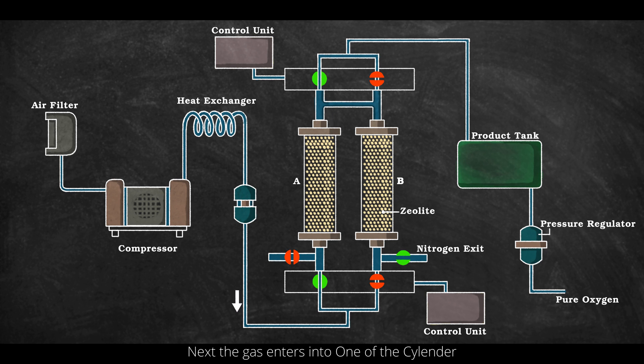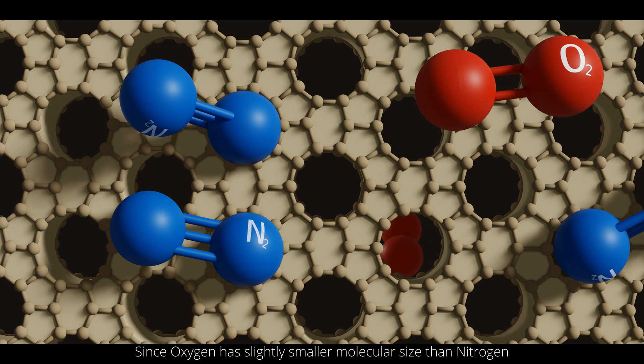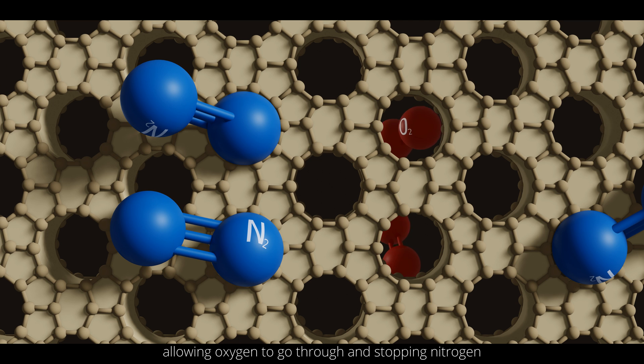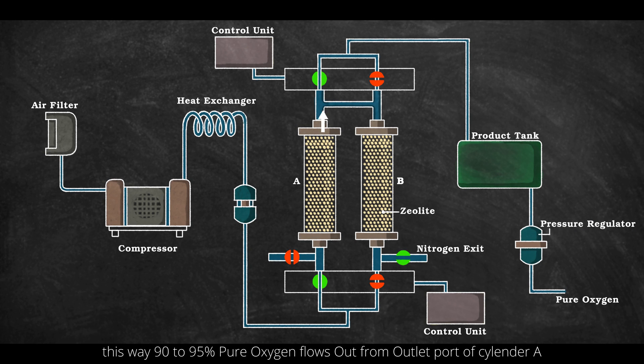Next, the gas enters into one of the cylinders — let's call it Cylinder A. Inside the cylinders, there is a substance known as zeolite, which is made up of porous crystals and acts as a sieve. Since oxygen has a slightly smaller molecular size than nitrogen, it allows oxygen to pass through while stopping nitrogen, so 90-95% pure oxygen flows out from the outlet port of Cylinder A.